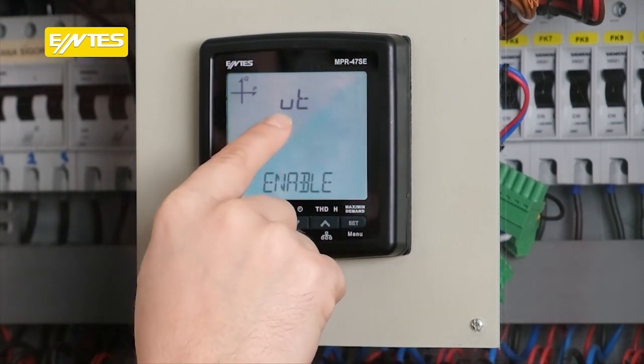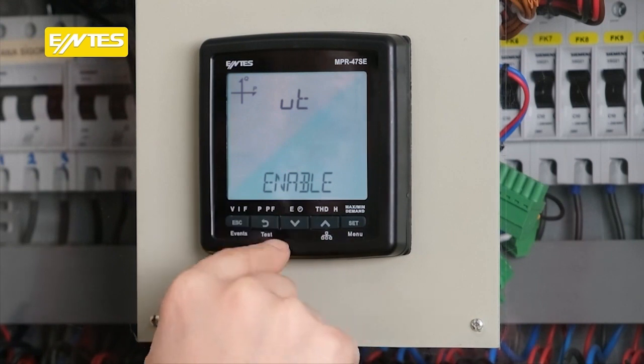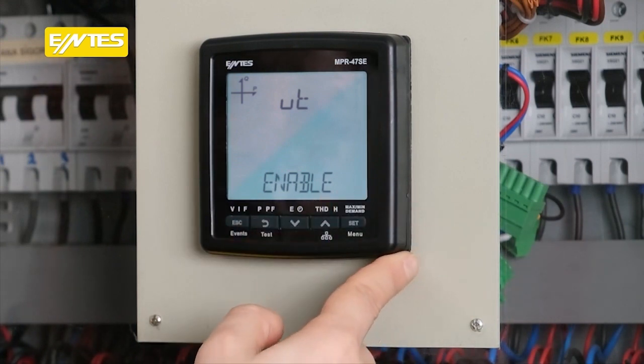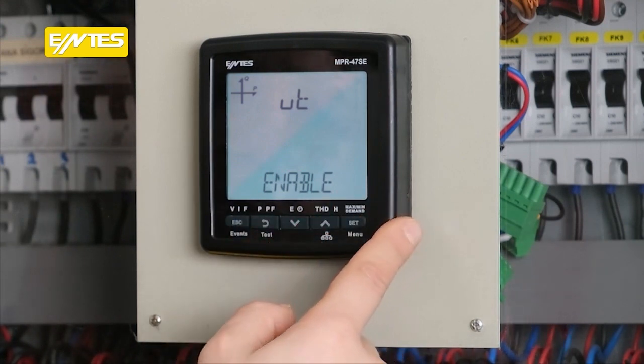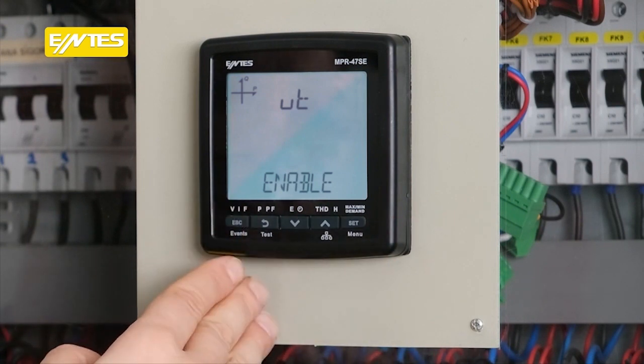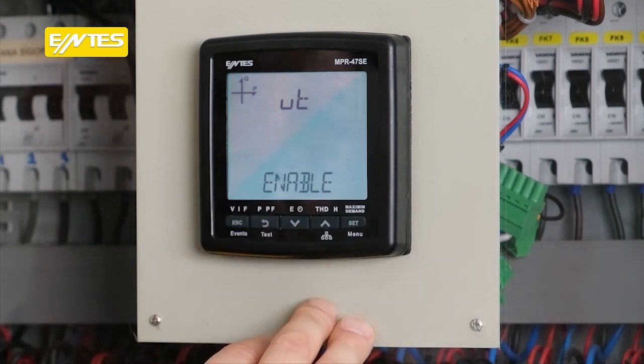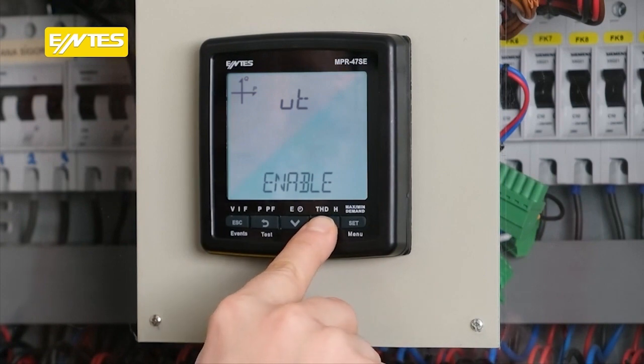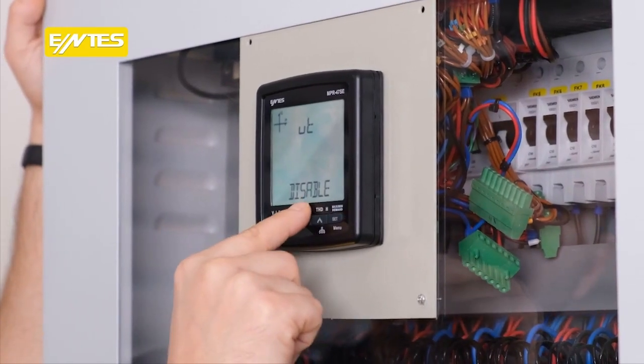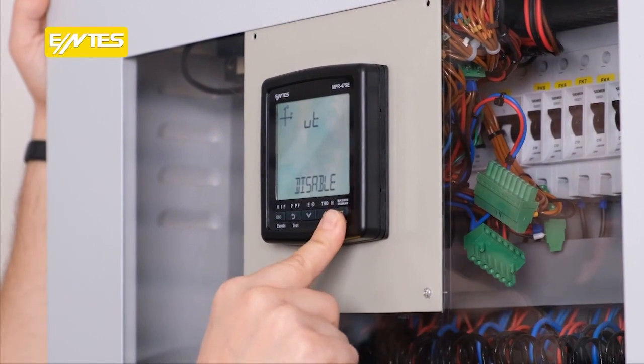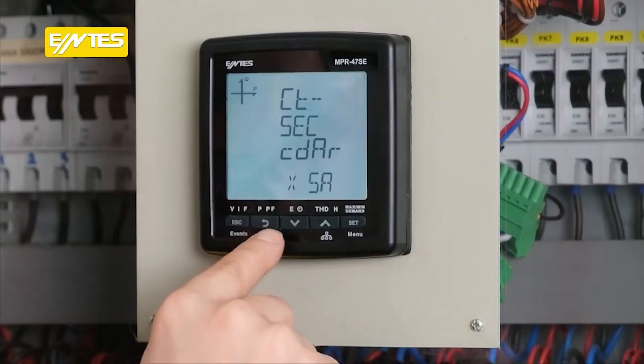Here we are greeted by a step-up transformer. If we use a voltage transformer in the network, when we activate and set it, it asks for the primary and secondary ratio of the voltage transformer. Enter the values. In this step, we don't use a voltage transformer, so we put it in passive mode. Look, it went out again next to me. We pressed the button, we approved.